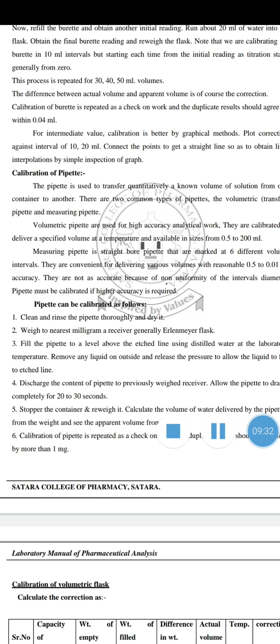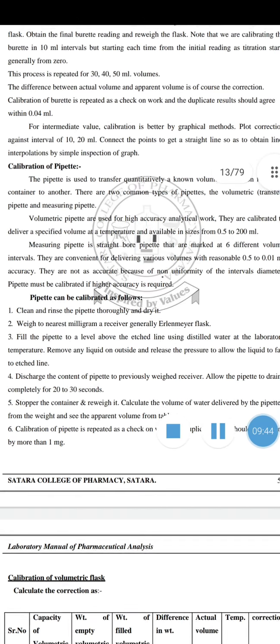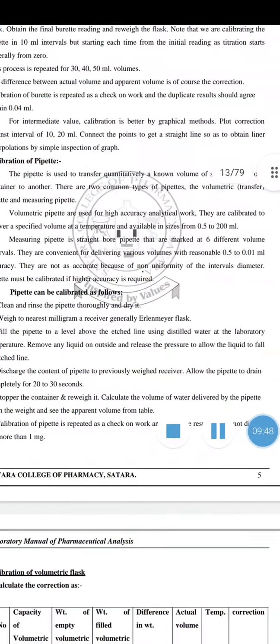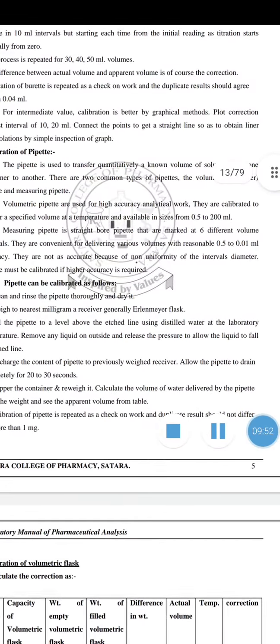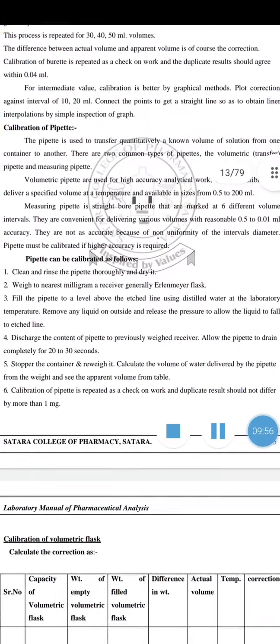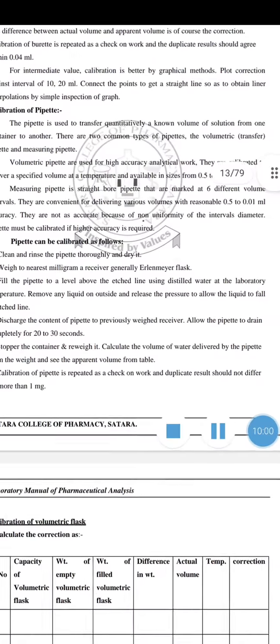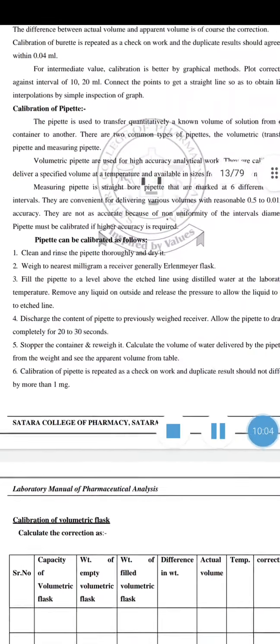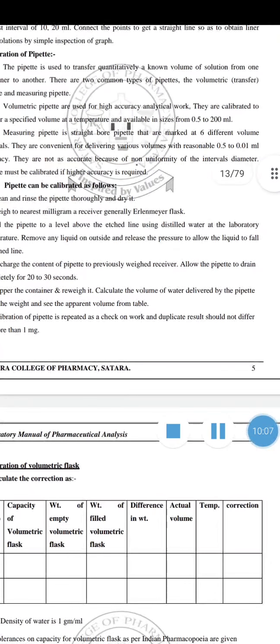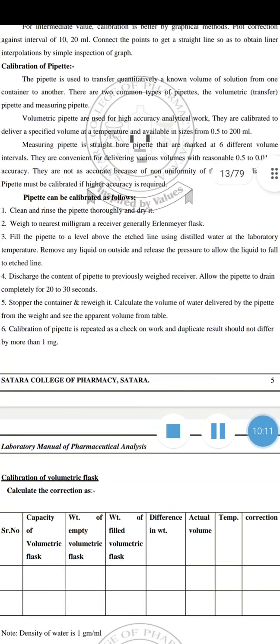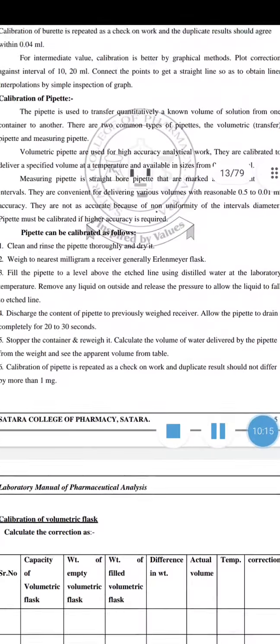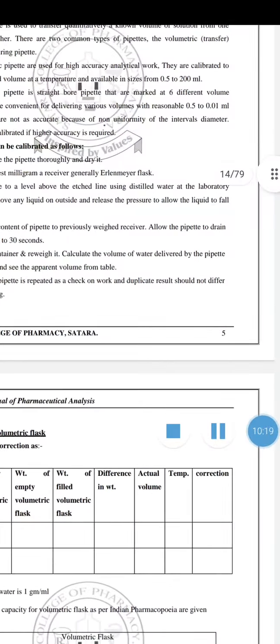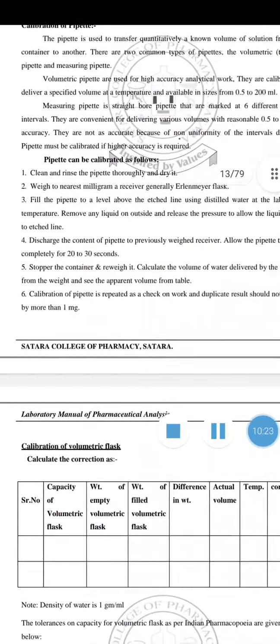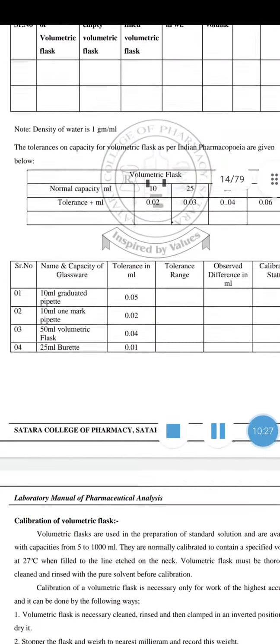Then a pipette can be calibrated as follows: clean and rinse the pipette thoroughly and dry it. Then weigh to the nearest milligram the receiver, generally an Erlenmeyer flask. Then fill the pipette to a level above the etch line using distilled water at the laboratory temperature. Remove any liquid on the outside and release the pressure to allow the liquid to fall to the etch line. Then discharge the content of the pipette into the previously weighed receiver. Allow the pipette to drain completely for 20 to 30 seconds. Then stopper the container and reweigh it. Calculate the volume of water delivered by the pipette from the weight and see the apparent volume from the table. Then calibration of the pipette is repeated as a check on work, and duplicate results should not differ by more than 1 milligram. This is the calibration of the pipette.